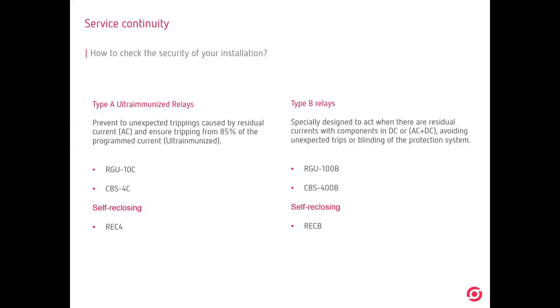The standard says if you have a mechanical one, not ultra-immunized, it could trip from 50 to 100. So if we have a relay set with 30 milliamps, with 16 milliamps, if it is not ultra-immunized, this can trip. 16, 17, 18, this can trip. Our devices, which are ultra-immunized, will ensure not tripping with values below 24 milliamps in this example of 30. It is always 85 up to 100%.